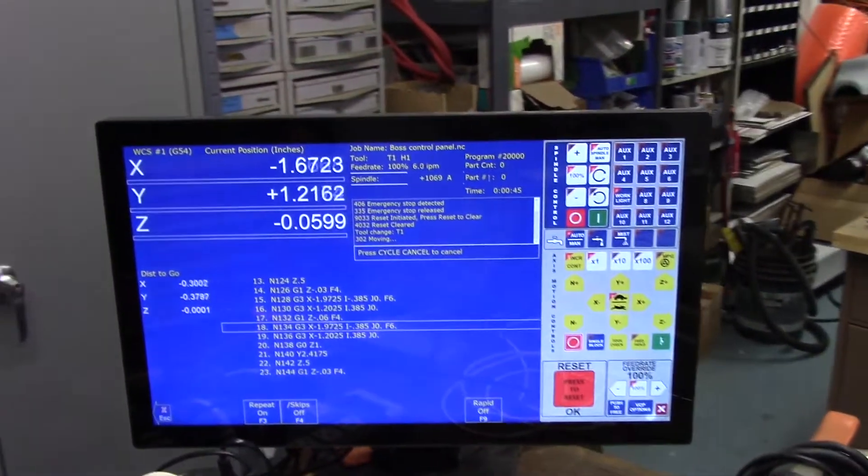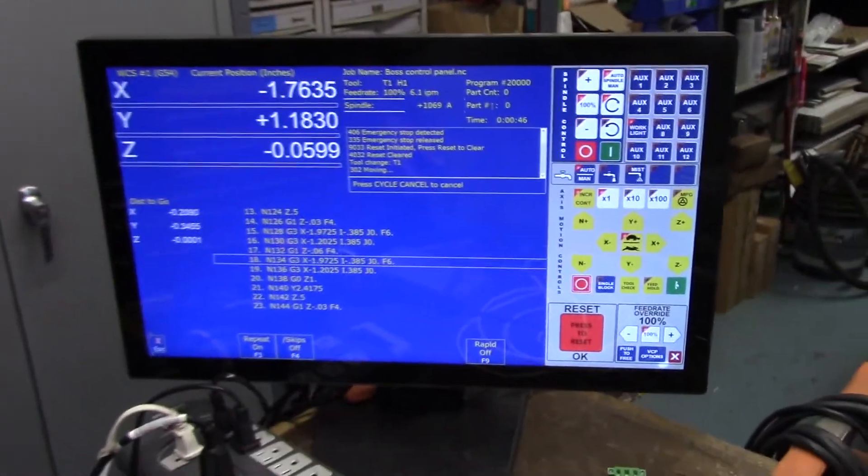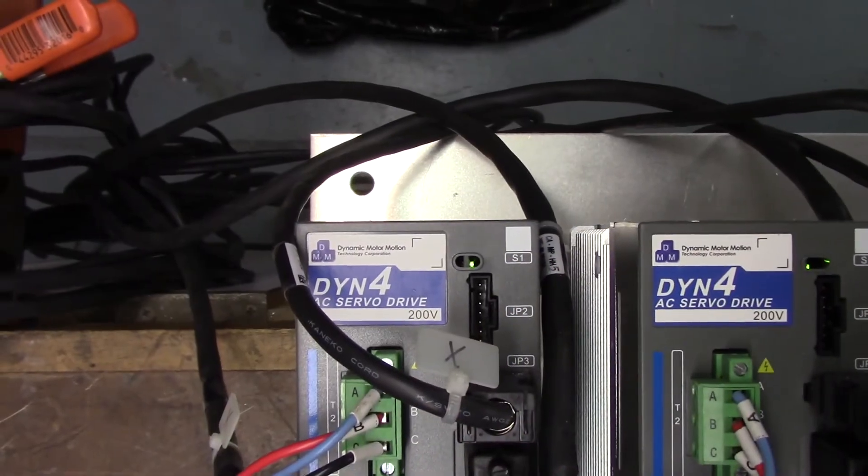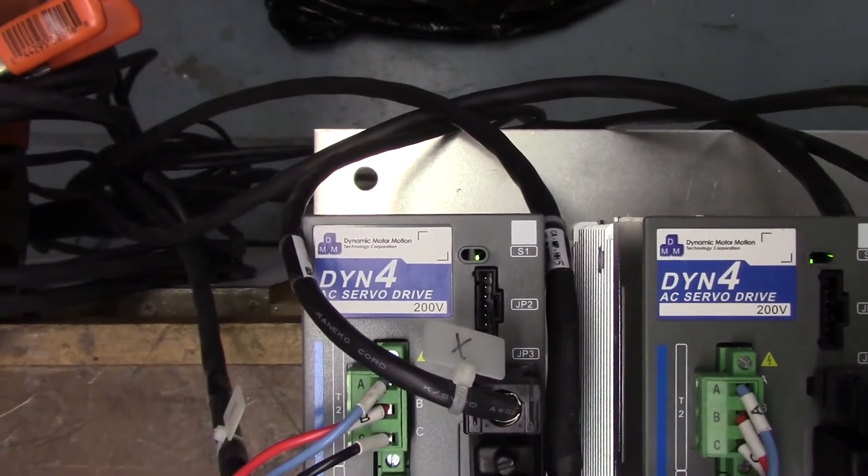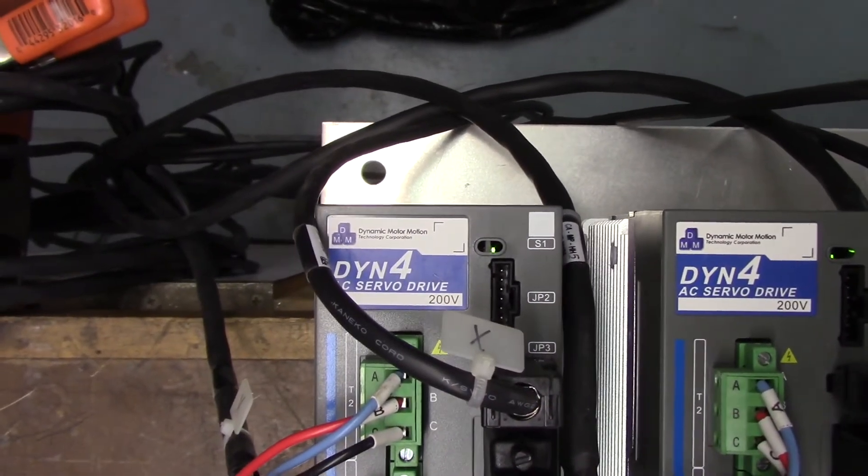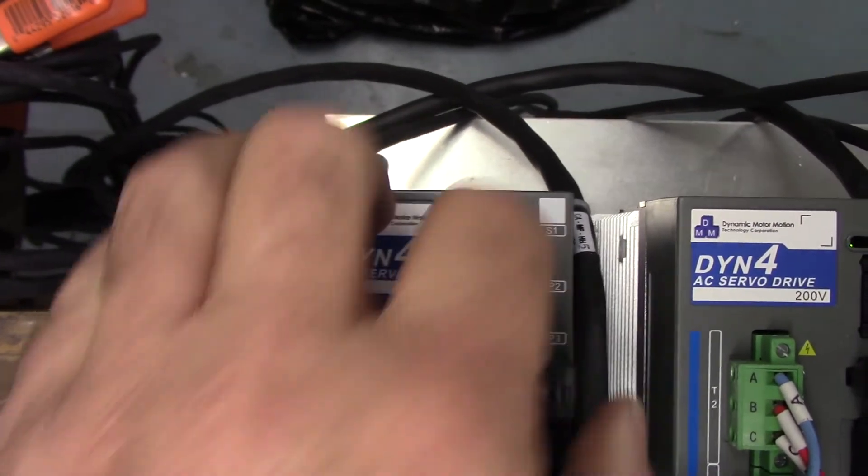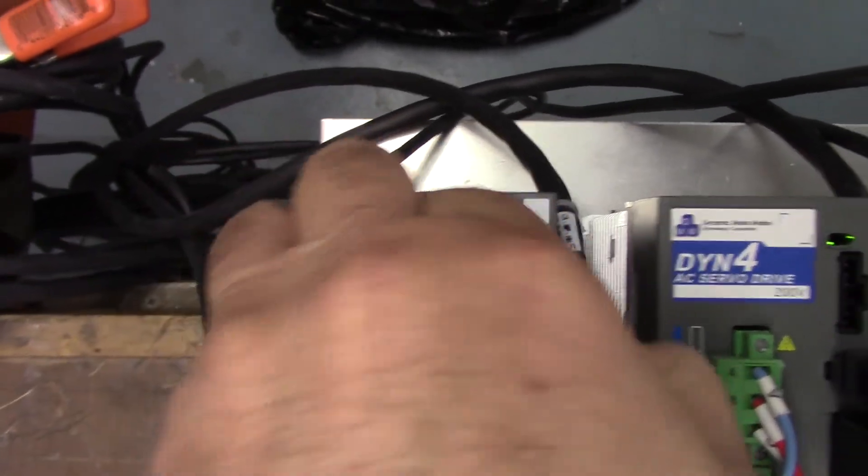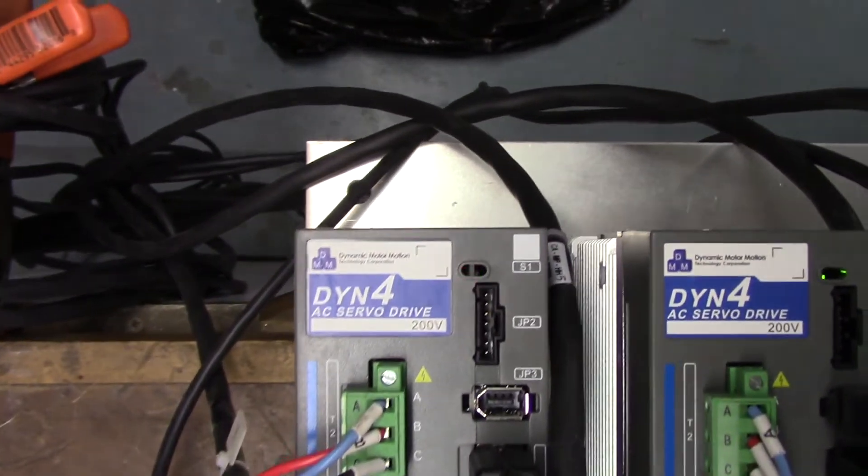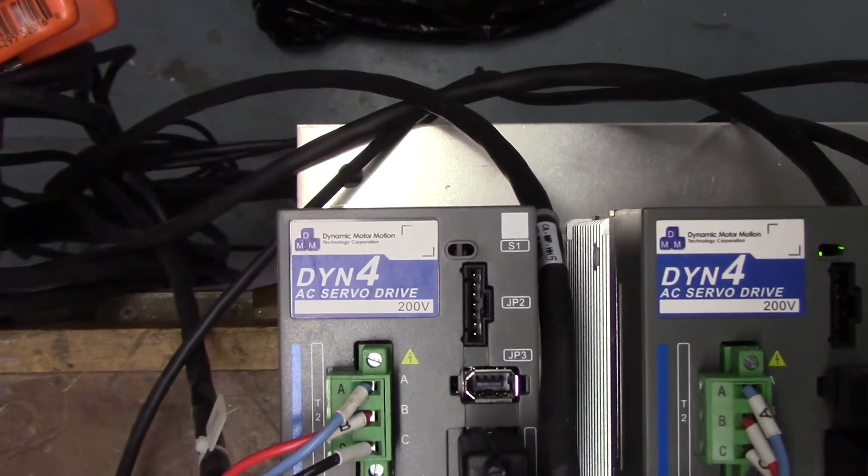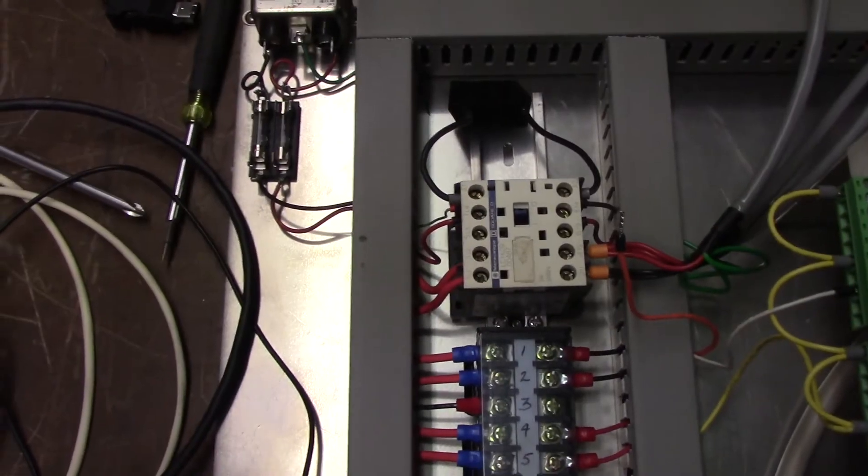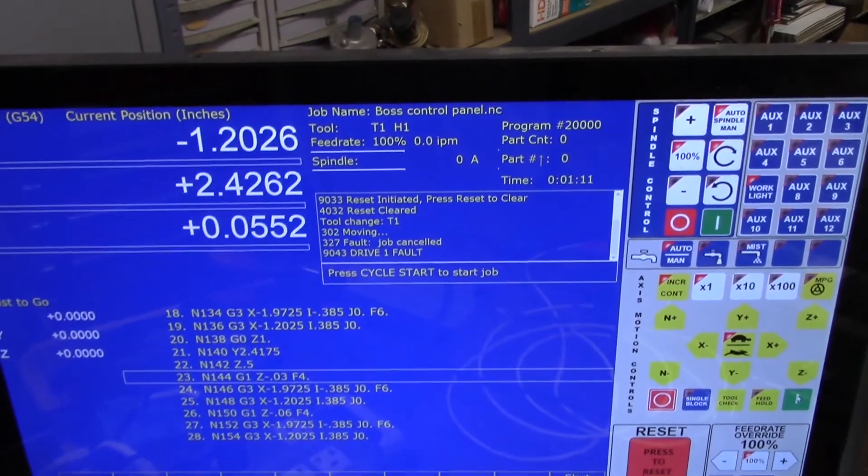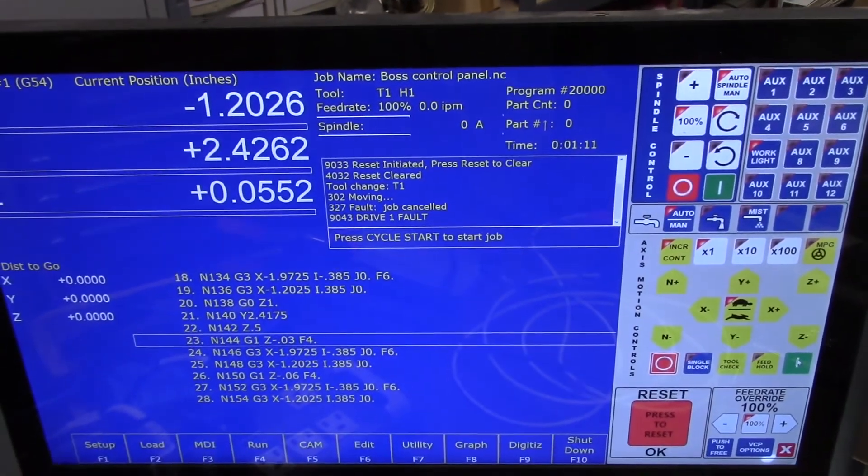What I'm going to do is cause a fault. Let me go over to this drive here - you can see the LED is green on that DYN4. I'm going to cause a fault by removing its encoder cable. You can see the LED blinking, the E-stop contact released, and we have a drive one fault.